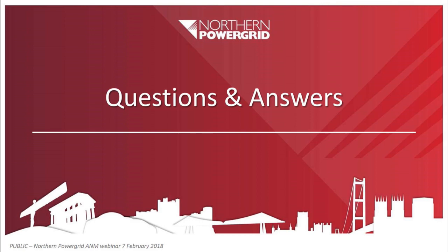Okay, thanks for that, Ian. So Bridget's asking us, how far have we got with generators joining the scheme so far? So what level of uptake has been completed to date? Yeah, so we've got 4 generators connecting to the ANM scheme at the moment. We've got 1 HV generator and another 3 EHV generators that are joining the ANM scheme, and they vary in size between around 3.5 megawatts up to around 10 megawatts each. So there's a wide range in capacities in there, and there's a mix of different generator types in there too.